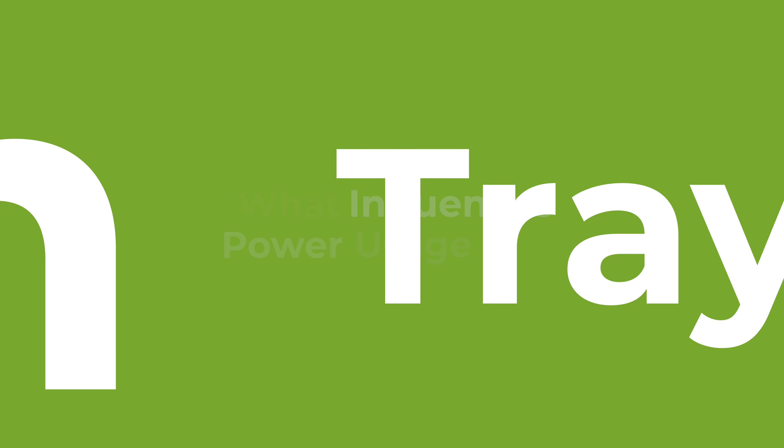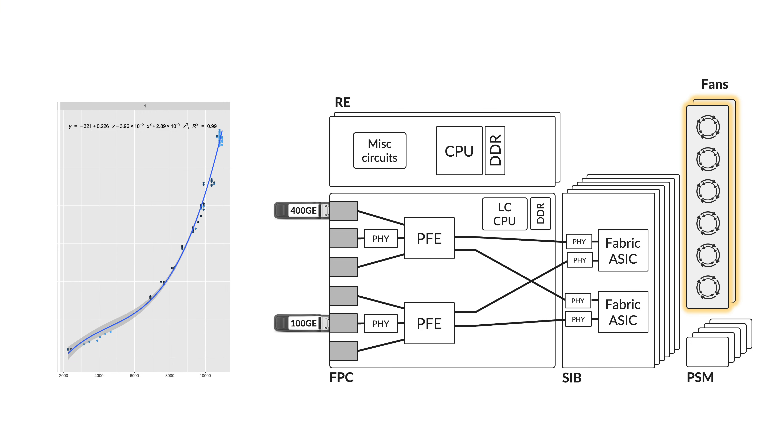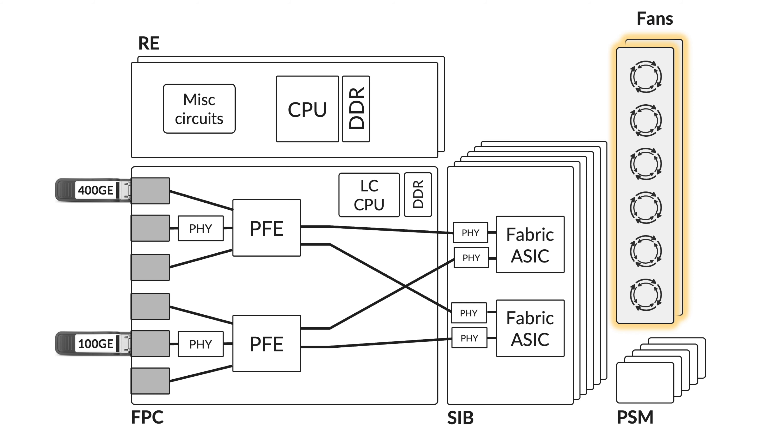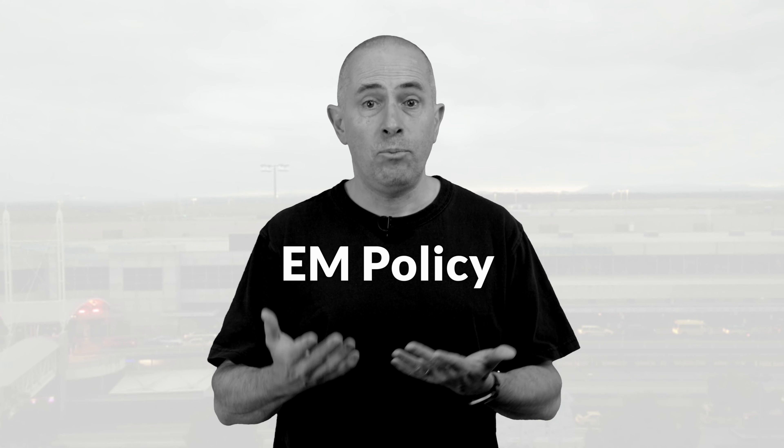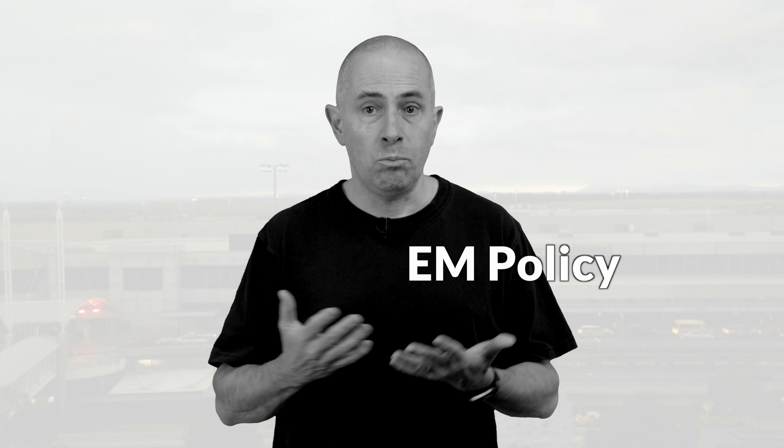Now let's look at the back of the chassis. The power consumption of a fan is a cubic function of the rotation speed, and this speed is influenced by the hottest point in the chassis. We have multiple sensors scattered all over the boards and components; the job of the fan is to make sure every part stays within operating limits. We have a mechanism called EM policy — EM for environment monitoring — that smartly adapts the speed of the fans to optimally reduce the temperature in the router.